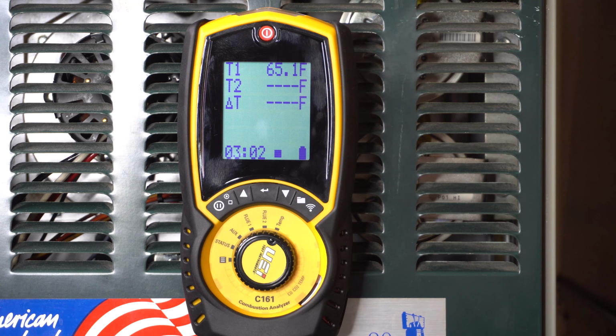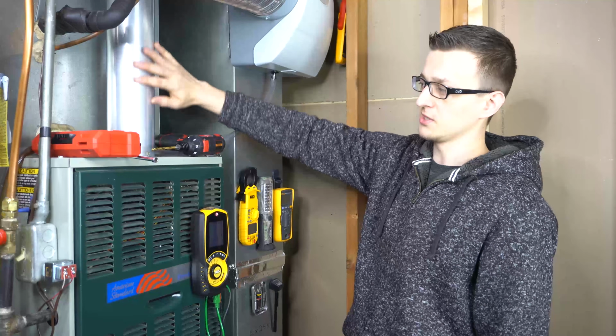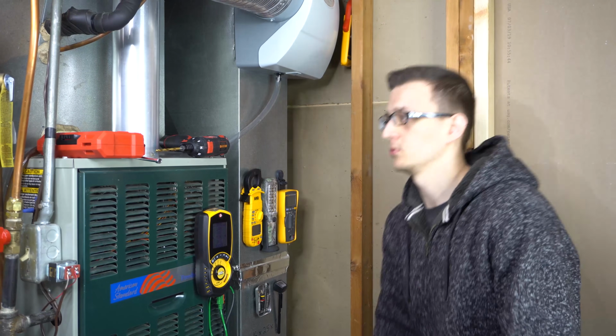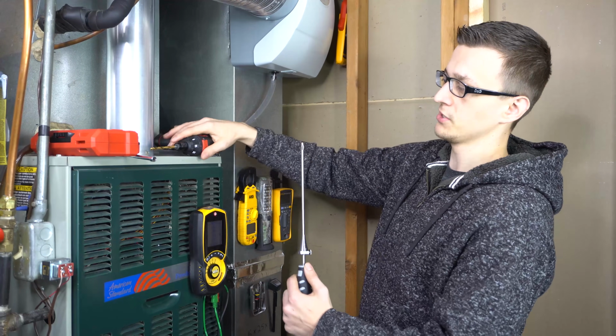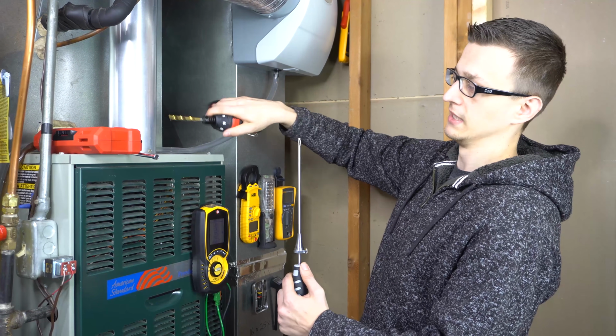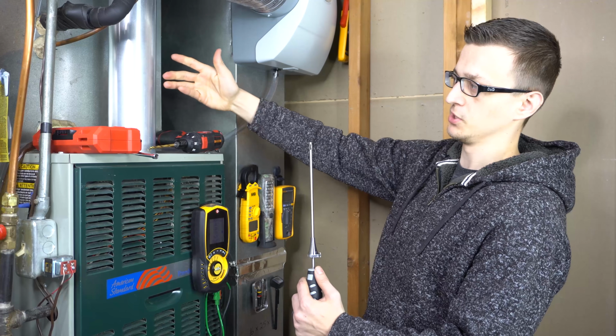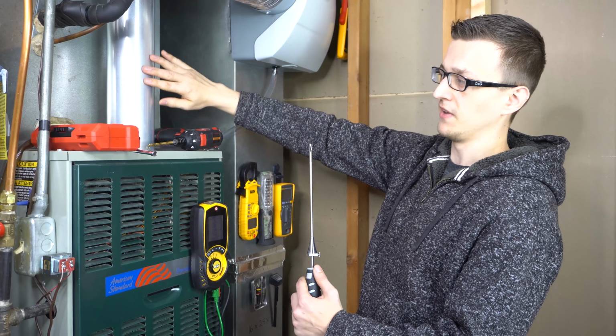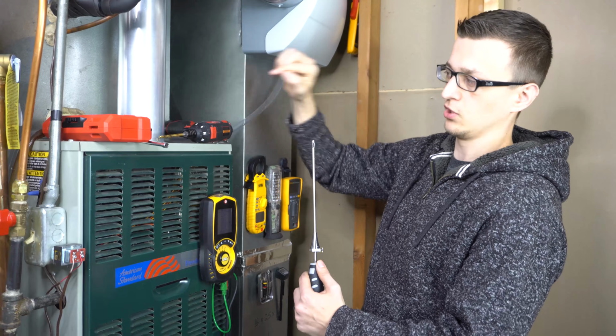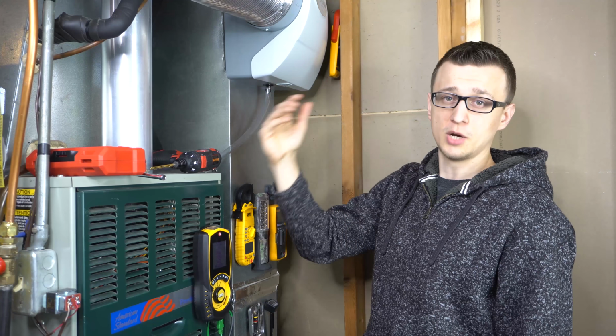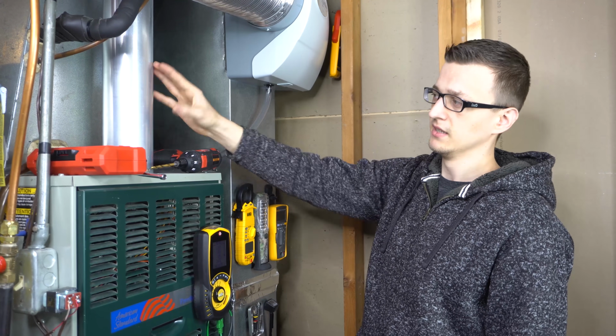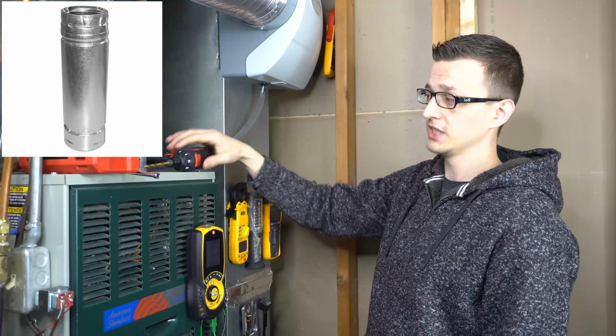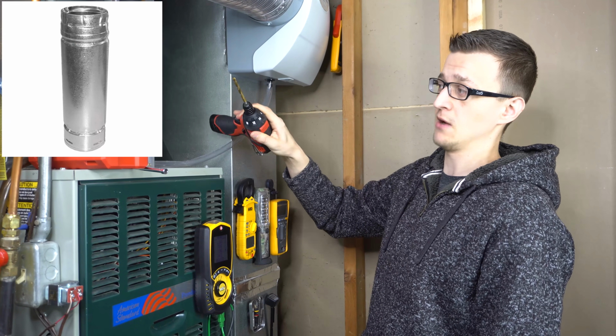Now let's actually go ahead and drill a hole in my vent and fire the furnace up and get some real readings going. Okay, so here's my furnace venting, and before I'll be able to put my test probe in there, of course I have to drill a hole in my vent. Now for my vent, which is a type C single wall vent, that is okay to just drill a hole right in it. But if you have a double wall type B venting, it's bigger and it has two walls to it, you should not be drilling holes in that one.